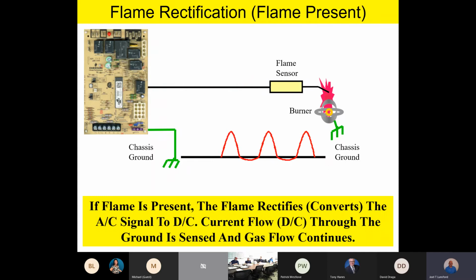Now watch this. When we put a flame to that flame sensor, the AC voltage goes through the flame sensor, actually goes through the flame itself, and then to chassis ground, because the burner's grounded. And this is really, really important. If a flame is present, the AC voltage goes through the flame, and the flame actually rectifies, or cuts, that voltage signal in half. We see a pulsating DC voltage going back along the ground plane to the control board.